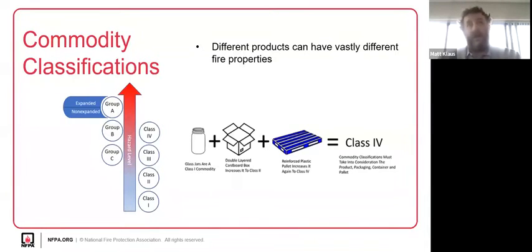But even starting with that lowest class, like a glass jar that I don't really worry about tremendously when I think about a fire originating there, I don't get to just look at the thing I sell or store. How am I packaging it? Am I putting it in a box full of styrofoam packing peanuts? Well, the glass is not my problem anymore, it's that styrofoam packing peanut or bubble wrap I have to protect because it's fragile. I start moving up that ladder as I package my goods, carton them in a cardboard box, then put them on a pallet. If I pick a wood pallet, that means something; if I pick a plastic pallet, I've increased that fire hazard and the commodity class I now have to protect. That might mean I need a bigger sprinkler system.